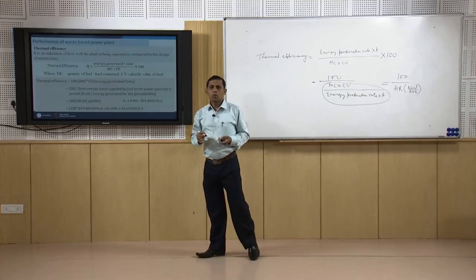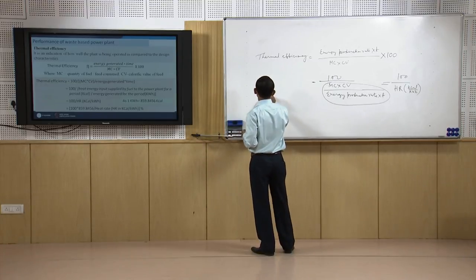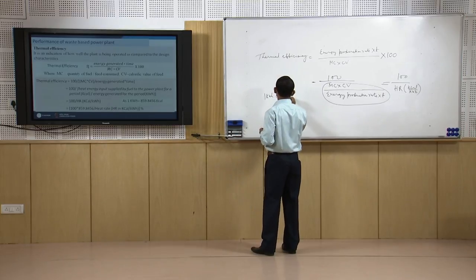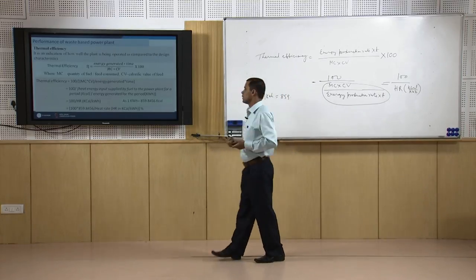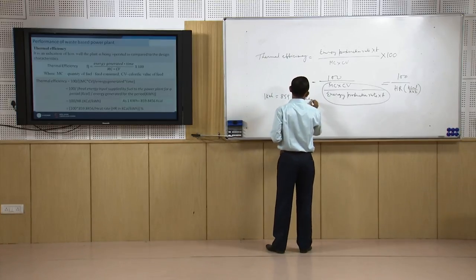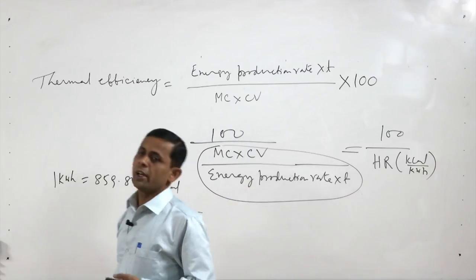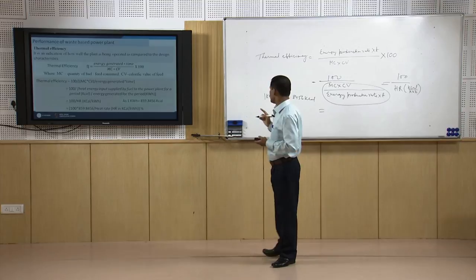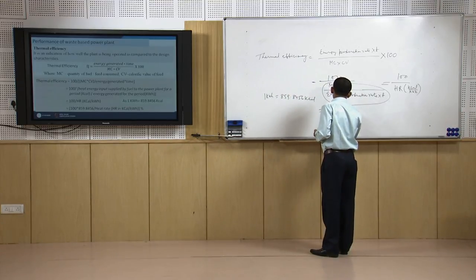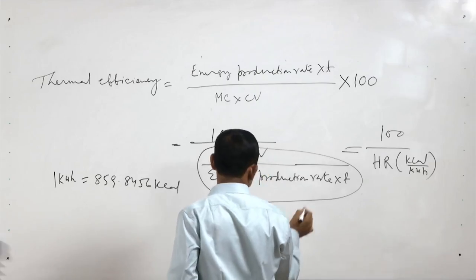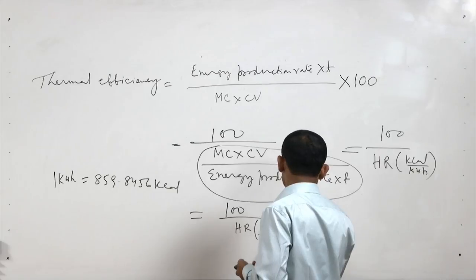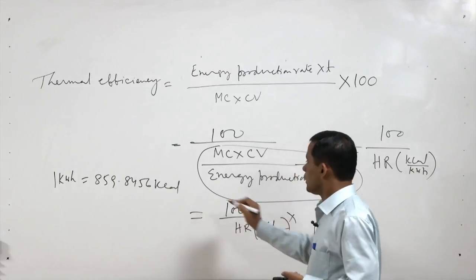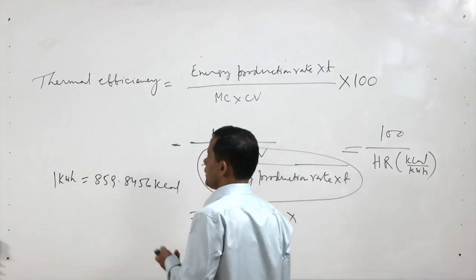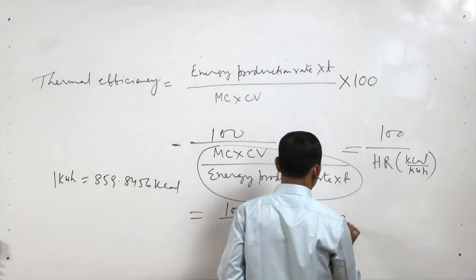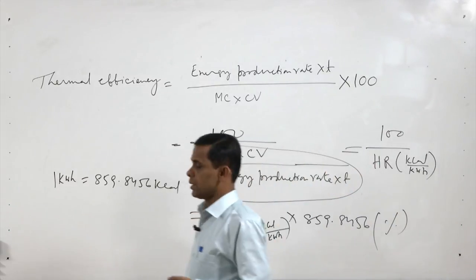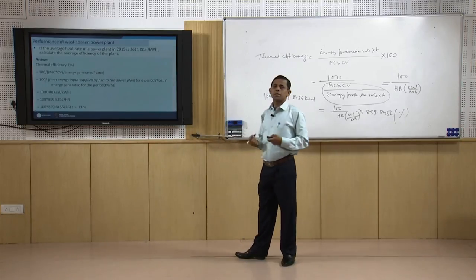Now we know that 1 kilowatt hour is equal to 859.8456 kilocalorie. Thus if we want to get the thermal efficiency in terms of percentage from the heat rate, we can write it as equal to 100 divided by HR in kilocalorie per kilowatt hour, into this conversion factor 859.8456, in percentage. Now let us calculate the thermal efficiency of a plant.